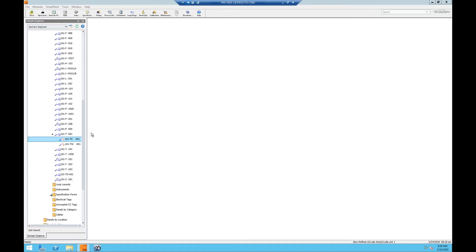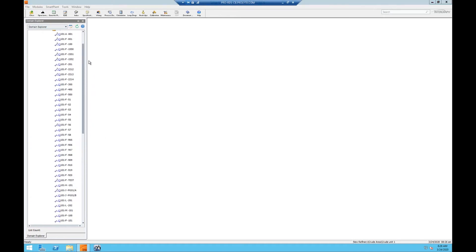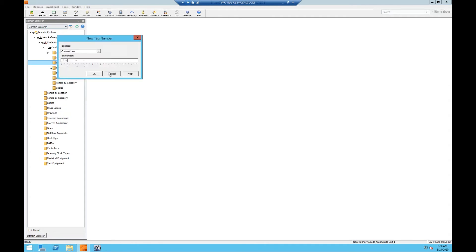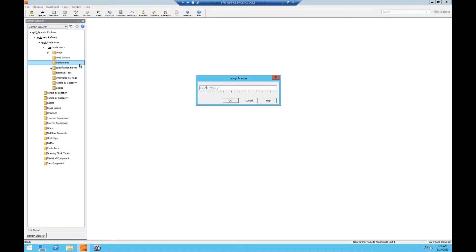We can also create a new tag from the Instruments folder. We can right-click the folder, click New, and click Instrument. It will ask us to create our new tag number, which we'll name TT-001. The Loop Name window will open, and notice that the loop has already been auto-filled. This is because SPI assumes what loop the instrument will be assigned to based on the first letter of the instrument type and the tag number.